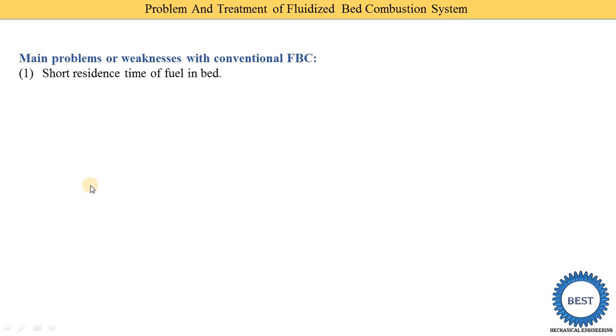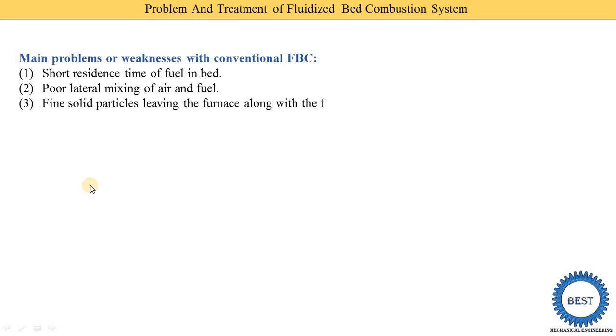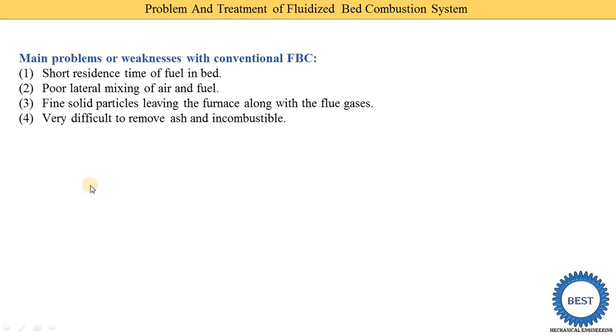The first problem is short residence time of fuel in the bed, meaning the fuel stays in the bed for a short time. Second, poor lateral mixing of air and fuel means the mixing of air and fuel is not done perfectly. Third, fine solid particles means the particles have a small size and leave the furnace along with the flue gases. Fourth, it is very difficult to remove the ash. So these are the four problems.